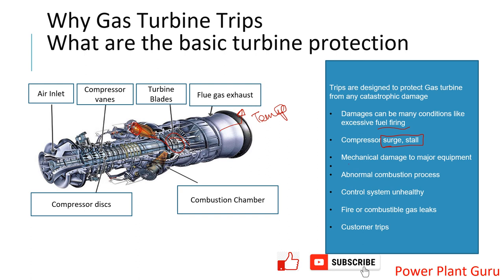The next concern is mechanical damage to major equipment. Let's say you are operating a gas turbine and the lube oil pump for bearing lubrication starts delivering low pressure day by day, and your lube oil header pressure keeps decreasing. Do you want to continue gas turbine operation with reduced lube oil pressure? Definitely not, because bearing lubrication will be decaying over time and the heat extracted from the bearings will also be reduced. So lube oil pressure low trip and bearing high temperature trip are there to prevent such mechanical failures.